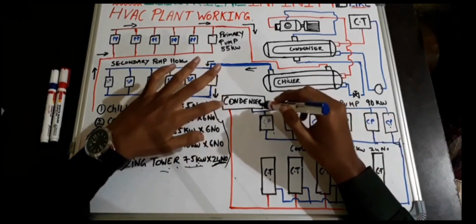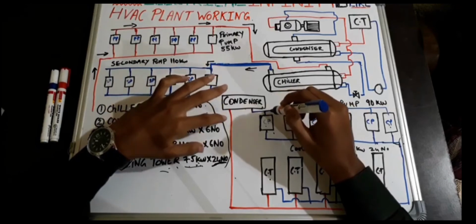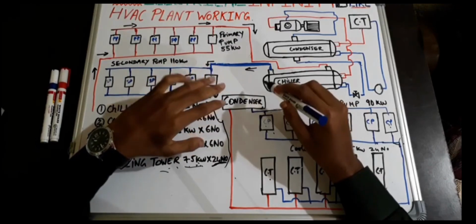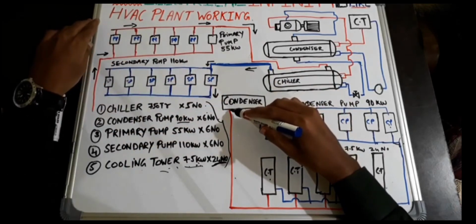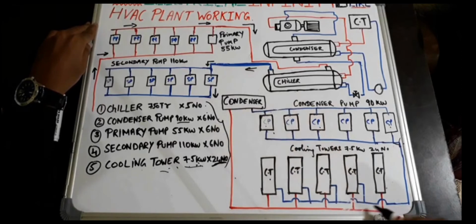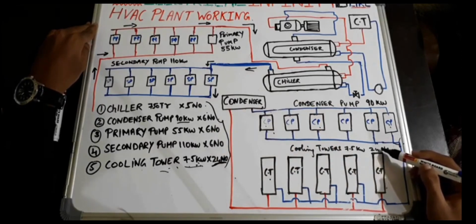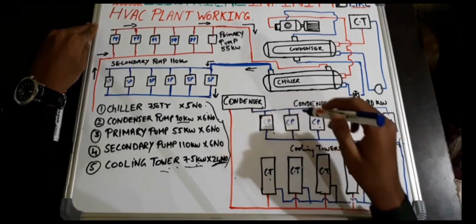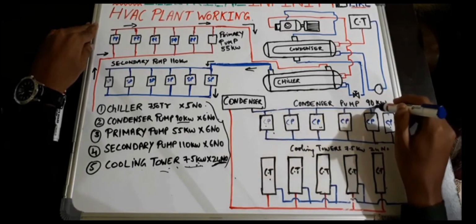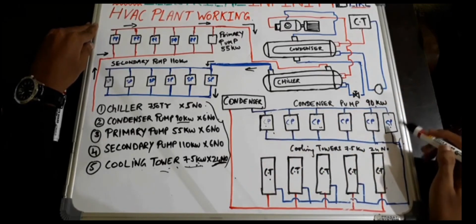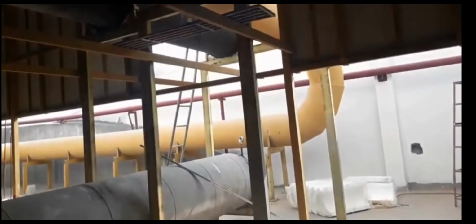After the pumping of cool water into the condenser, heat exchange takes place between the cool water and the condenser refrigerant. After that the water gets heated up and the refrigerant gets cool, and the heated water is again transferred to the cooling tower, as you can see here. Again the hot water is cooled in the cooling tower and this cool water is transferred to the condenser with the help of these condenser pumps. Each pump is of 90 kilowatt and we have used 6 condenser pumps. This pipe is coming from the output of the 6 condenser pumps, which carries cool water from the cooling tower to the condenser. As you can see here, the yellow pipe at the back side of the condenser pumps the cool water into the condenser for cooling of the condenser refrigerant.